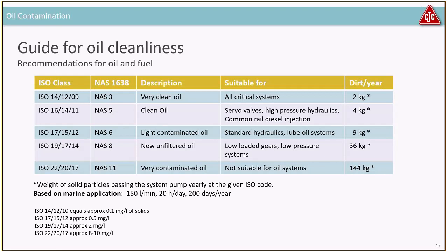Why you want to clean the oil: if you have an ISO class of 19/17/14 — similar to NAS 8 — this is suitable for low-loaded gears and low-pressure hydraulic systems. But running a system at 150 litres per minute, 20 hours a day, 200 days a year, will circulate 36 kilos (about 70 pounds) of dirt per year over the main pump, causing wear. With cleaner oil at 16/14/11 or NAS 5, you'd only circulate 4 kilograms (8 pounds) — a big difference. Cleaner oil is suitable for servo valves, high-pressure hydraulics, and common rail diesel.